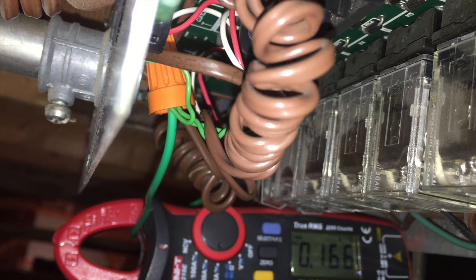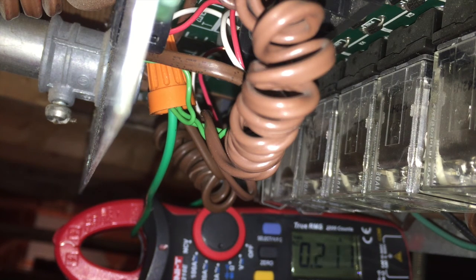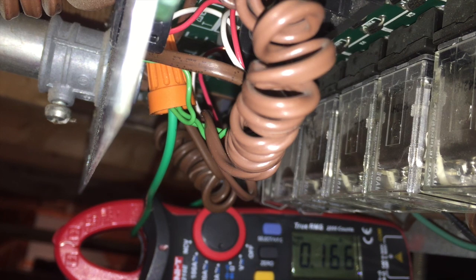Anyway, I feel pretty comfortable with this. I think I'm well within the margin for running 3 thermostats on this. Not sure about 4. Not sure I'd recommend that. You'd probably be under 400 most of the time, but there would be that big spike on power up, and I don't know if that's a good idea or not. I feel pretty confident with 3, 4 maybe kind of pushing it. More than that, I think you're definitely pushing it. So if you've got the six zone unit, then I think you need to look at a more complicated solution, with either replacing the transformer on the Taco with a bigger one, or having local transformers powering the Ecobees.